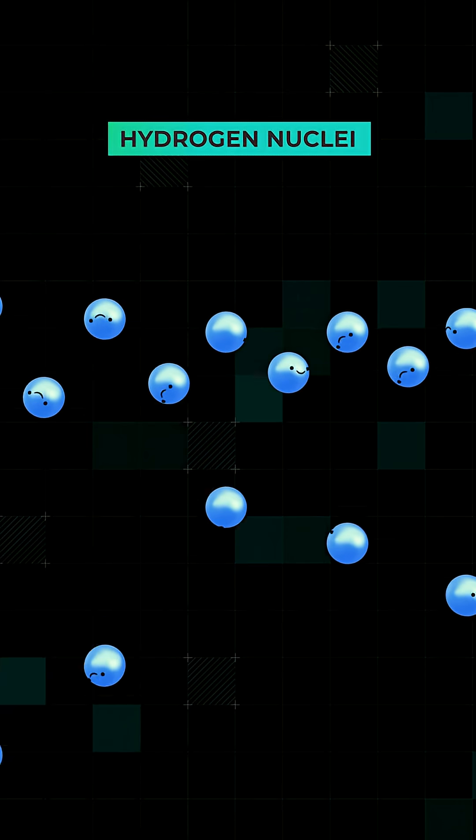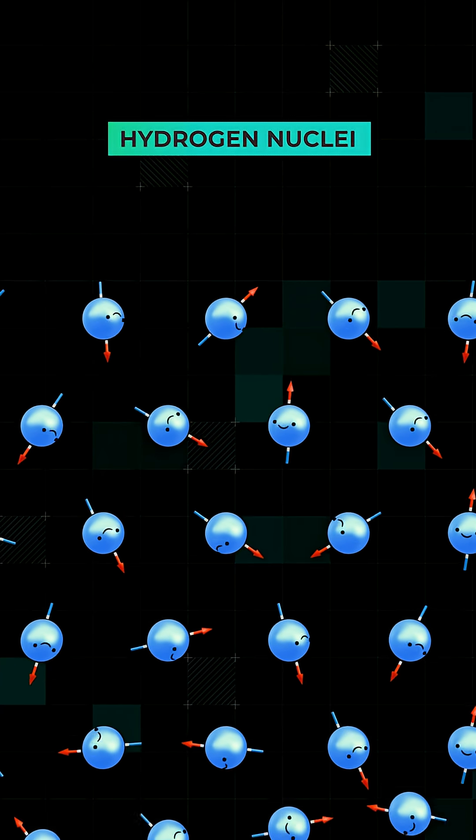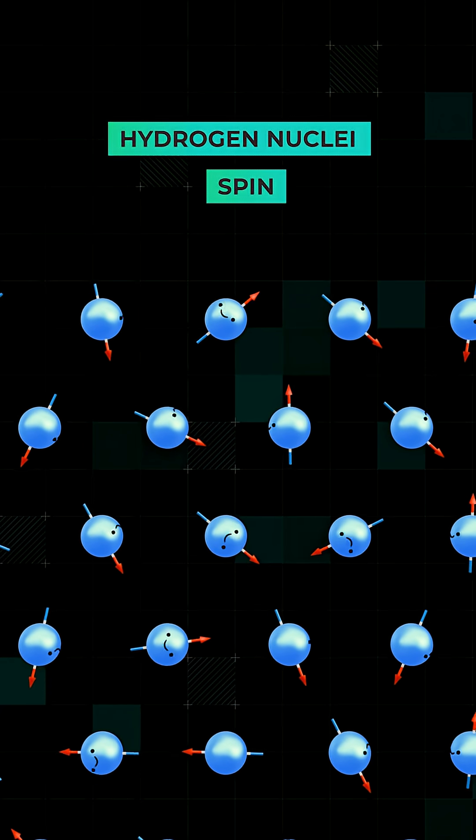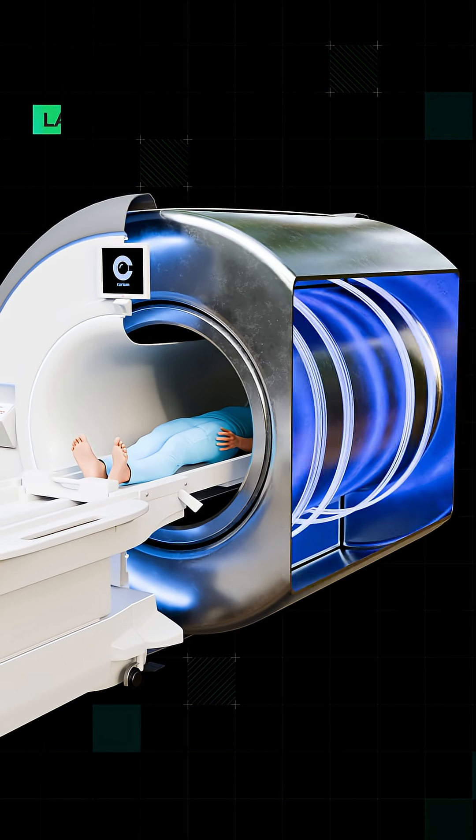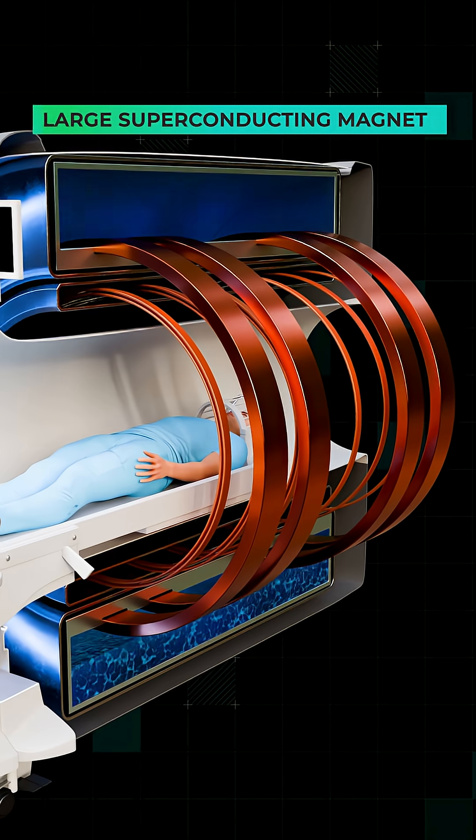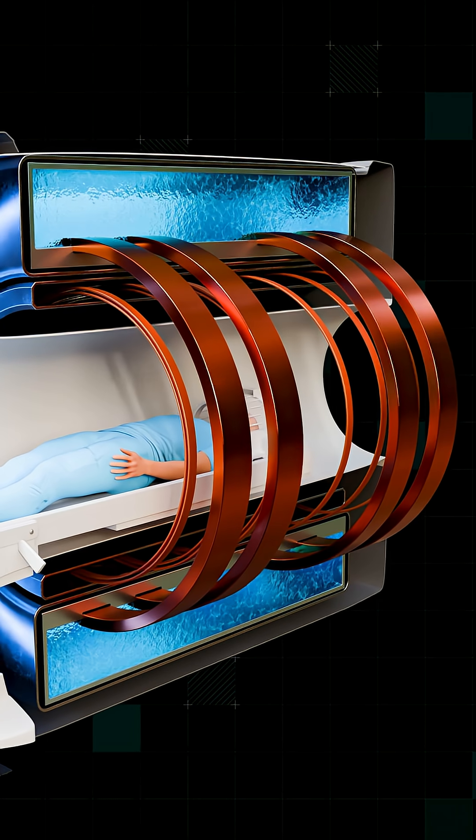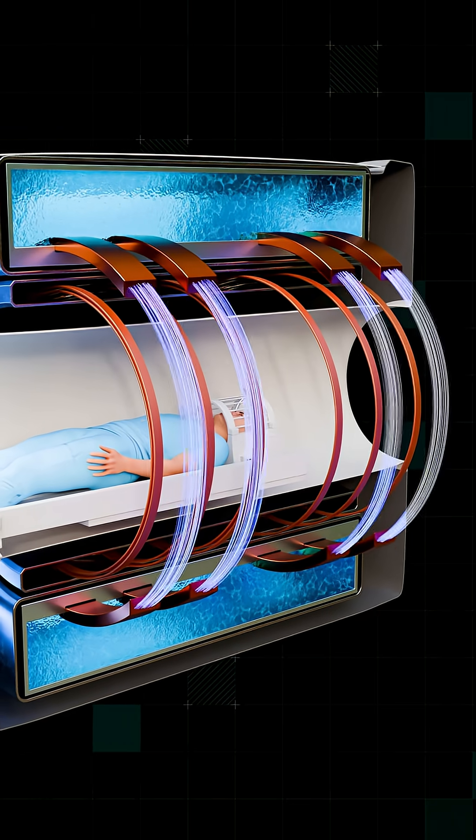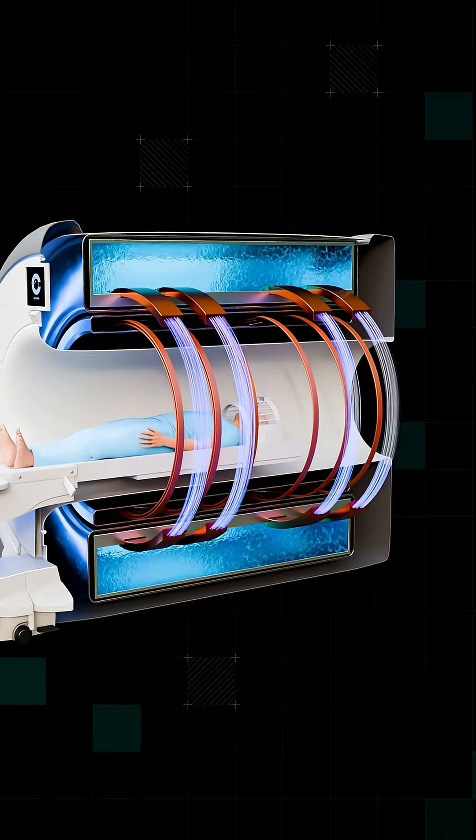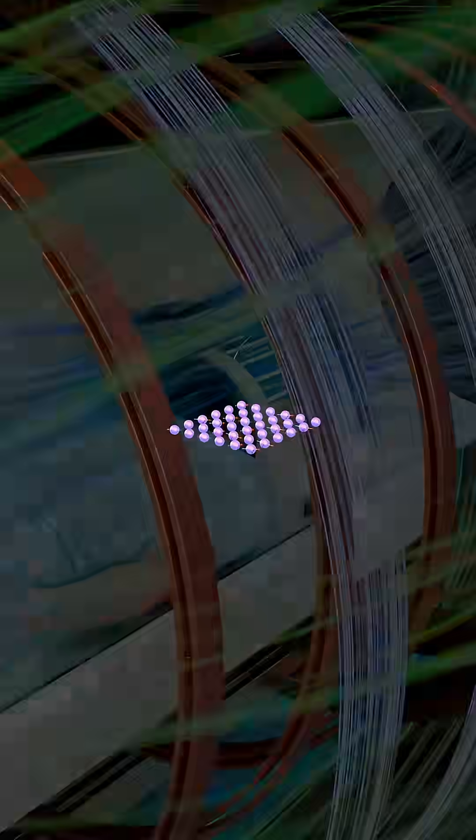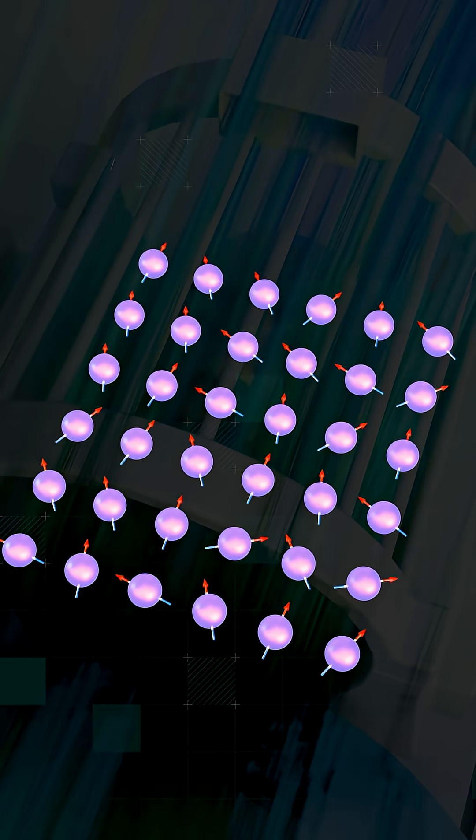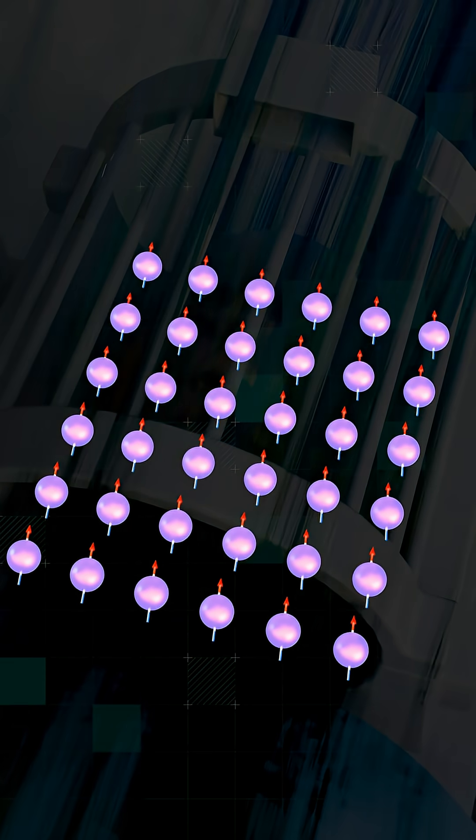Each hydrogen nucleus behaves like a tiny spinning magnet, a property called spin. To harness this property, MRI machines use a superconducting magnet chilled with liquid helium carrying enormous currents with zero resistance. Those circulating currents generate a very strong magnetic field. This powerful field forces all the hydrogen protons to align neatly along the longitudinal axis.